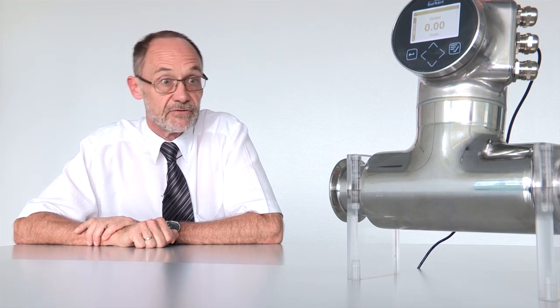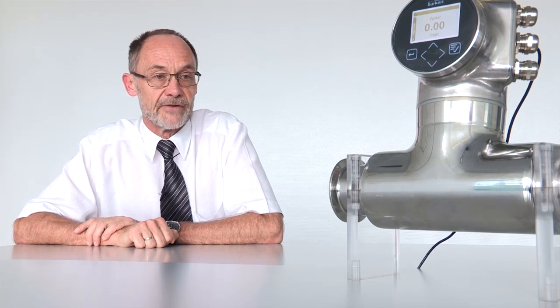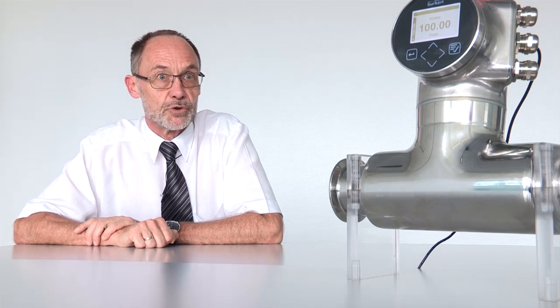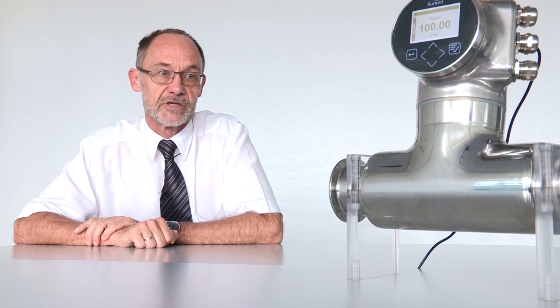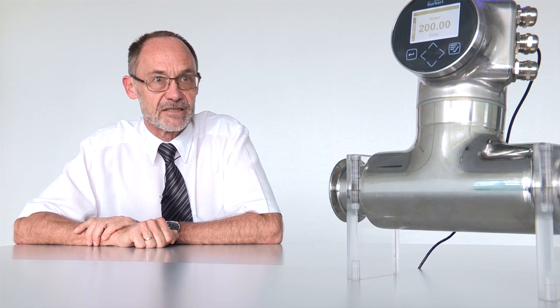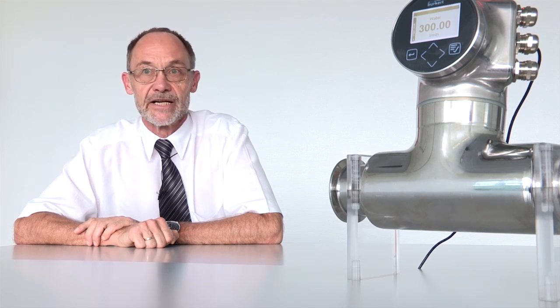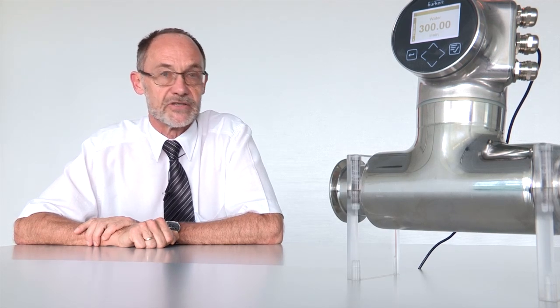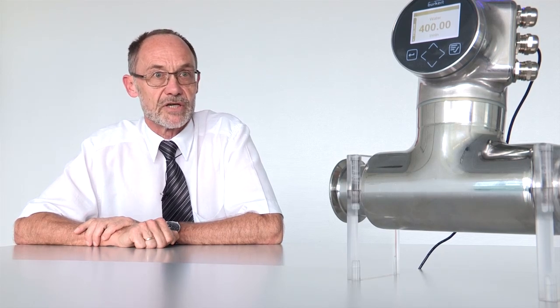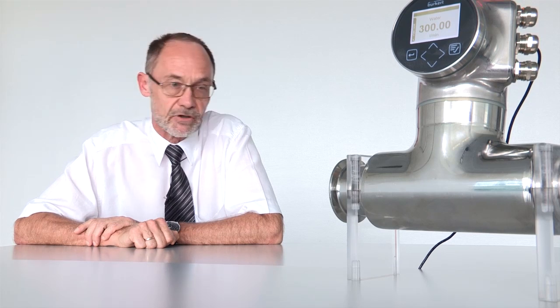This is not a problem with FLOWave. It's just a tube. Coriolis is built sometimes from two tubes, and the diameter in the measuring tube is different from the outside, giving a lot of things where customers have to take care. Even cleaning is not that easy, and pressure drop exists with Coriolis but not with FLOWave. It's a big list where customers really are keen on looking to FLOWave. The total cost of ownership for FLOWave is definitely lower than with Coriolis.